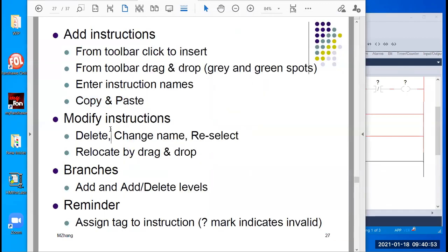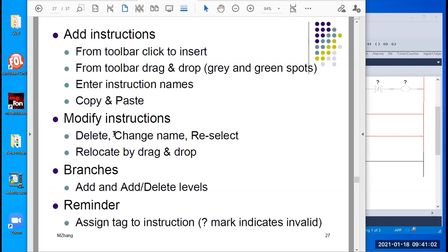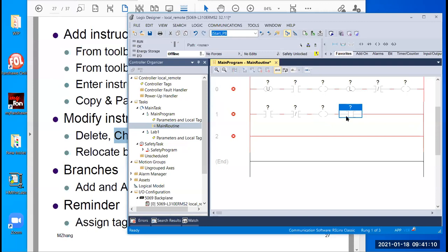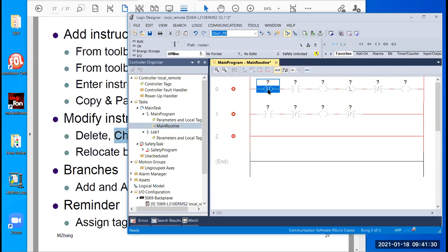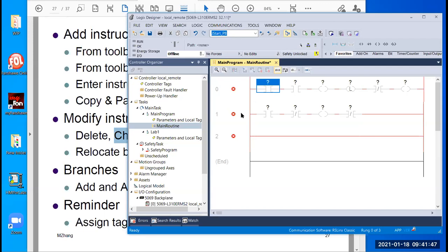This is how you add instructions. When you want to modify an existing one, you can delete — as already shown — by highlighting and pressing the Delete key. You can also change an instruction name: double-click it, it shows XIC, you can type in XIO to turn it to Examine Off. If you know the name and use the drop-down, when you click the drop-down you can select from the list — for example change to XIC Examine On — double-click and that changes it.